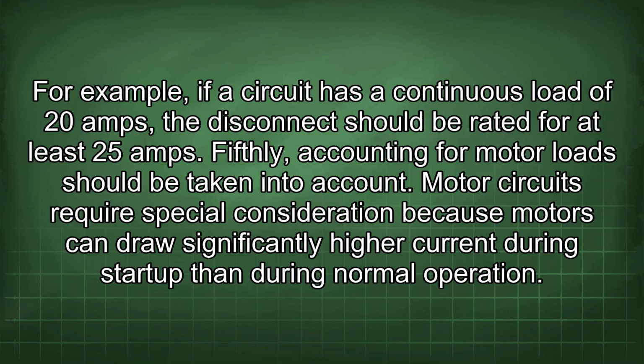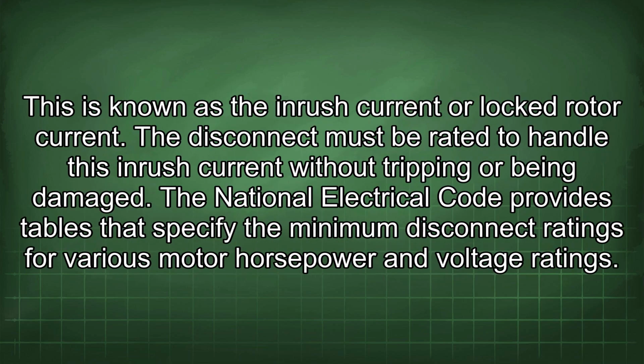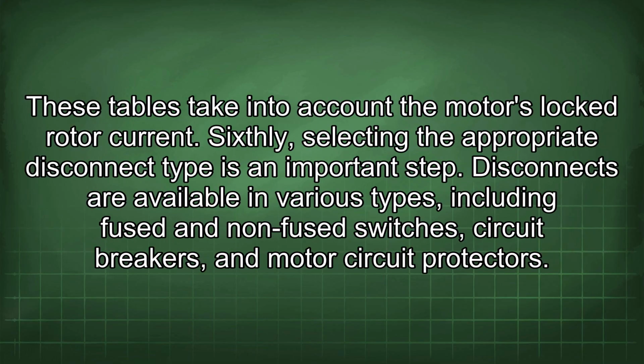Motor circuits require special consideration because motors can draw significantly higher current during startup than during normal operation. This is known as the inrush current or locked rotor current. The disconnect must be rated to handle this inrush current without tripping or being damaged. The National Electrical Code provides tables that specify the minimum disconnect ratings for various motor horsepower and voltage ratings. These tables take into account the motor's locked rotor current.